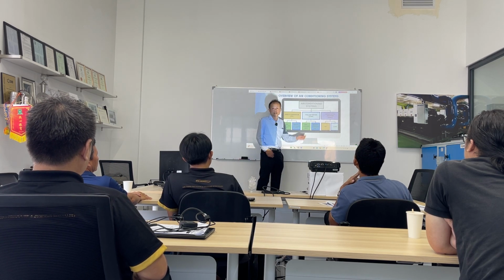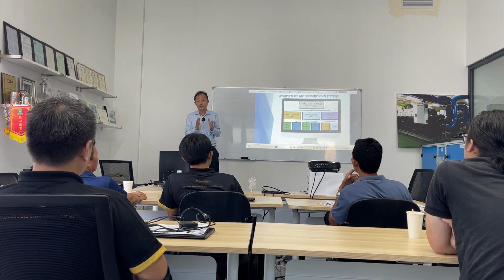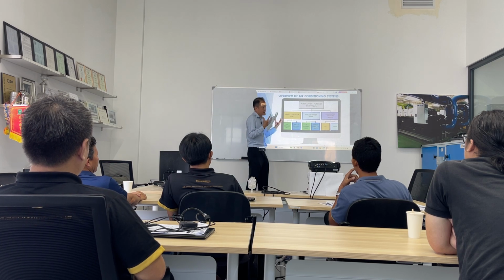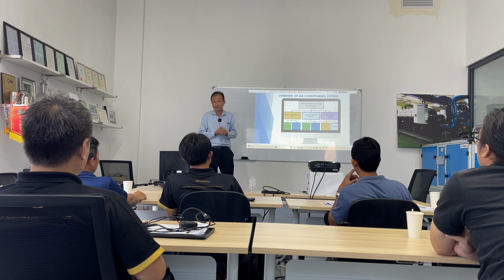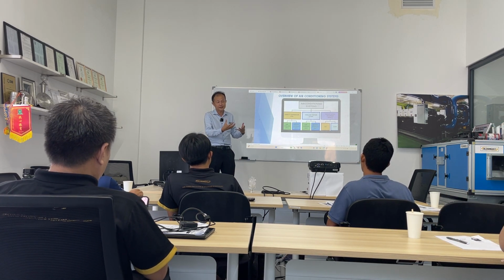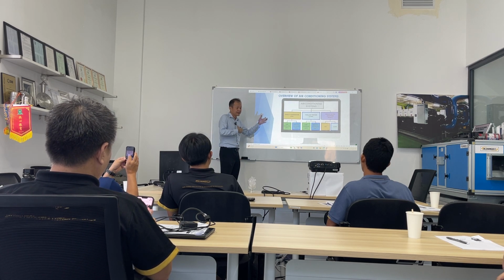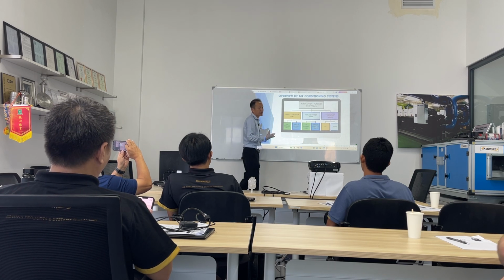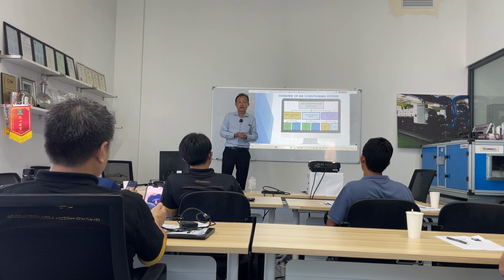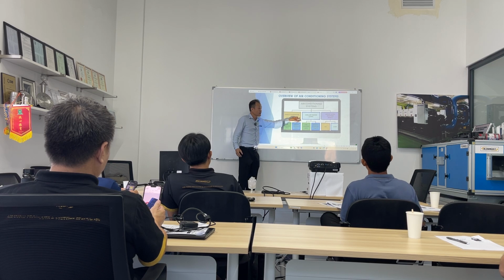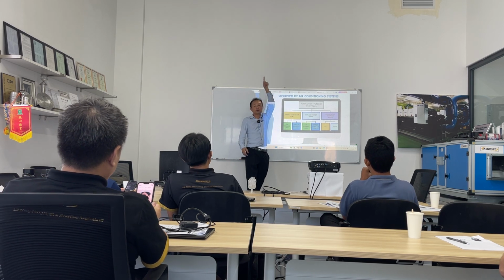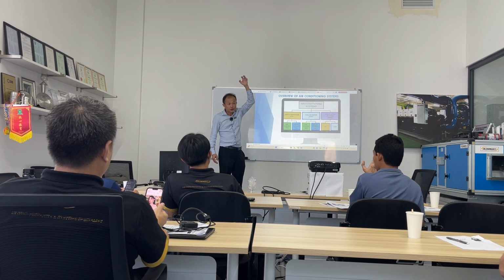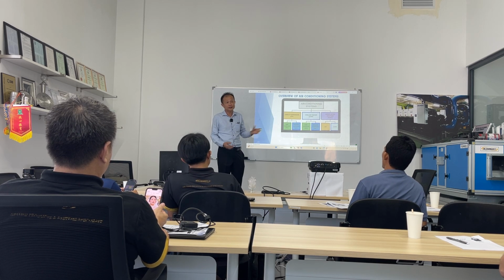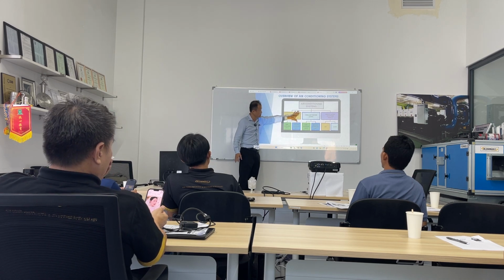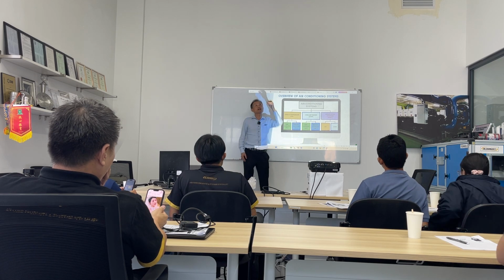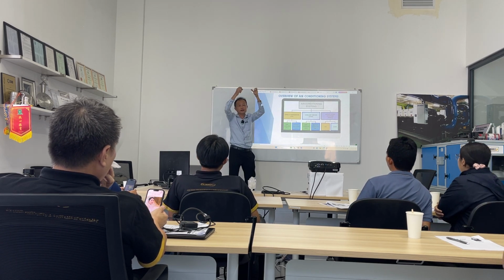Okay. Chill water system is no more direct refrigerant cooling the air. We have to isolate by using a centralized chiller system, where the chiller is stored in one of the central locations, and this chiller is running refrigerant within the machine itself, but at the same time producing chill water through the evaporator. And the chill water that is being generated is circulated by the pump through the chill water pipe and supplied into the coil here, where the chill water is cooling the air. We call it chill water system. Of course, I'm going to show you some sample designs.